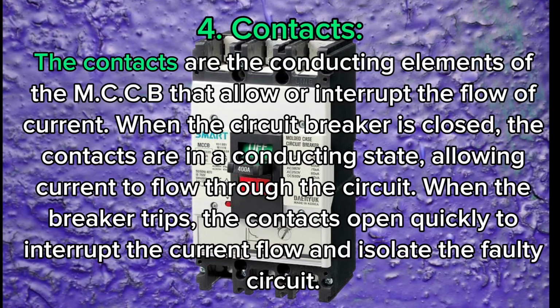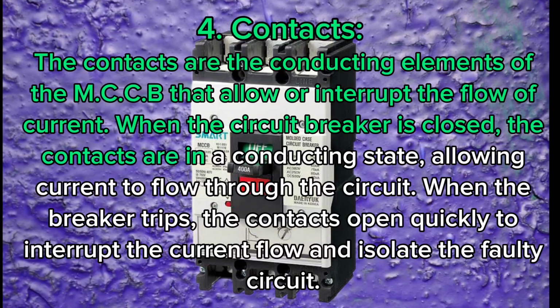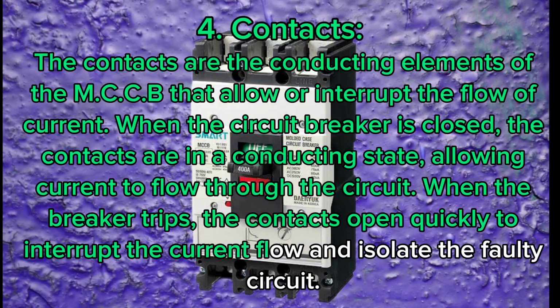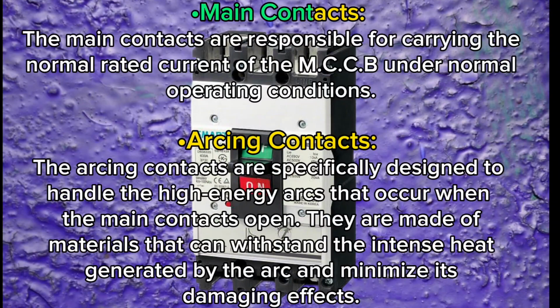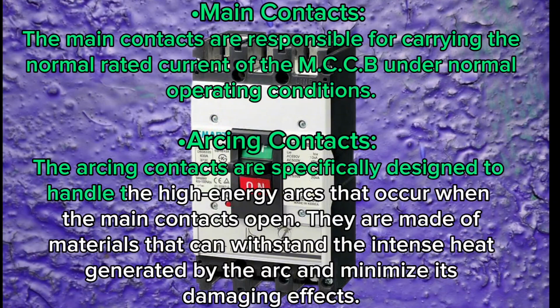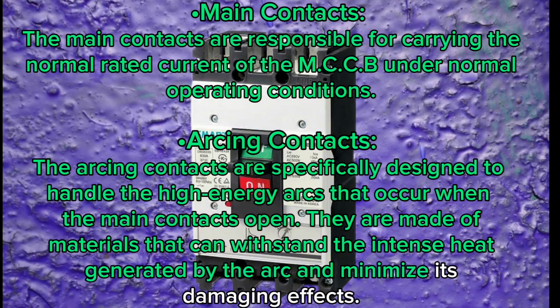4. Contacts. The contacts are the conducting elements of the MCCB that allow or interrupt the flow of current. When the circuit breaker is closed, the contacts are in a conducting state, allowing current to flow through the circuit. When the breaker trips, the contacts open quickly to interrupt the current flow and isolate the faulty circuit. Main contacts. The main contacts are responsible for carrying the normal rated current of the MCCB under normal operating conditions. Arcing contacts. The arcing contacts are specifically designed to handle the high energy arcs that occur when the main contacts open. They are made of materials that can withstand the intense heat generated by the arc and minimize its damaging effects.